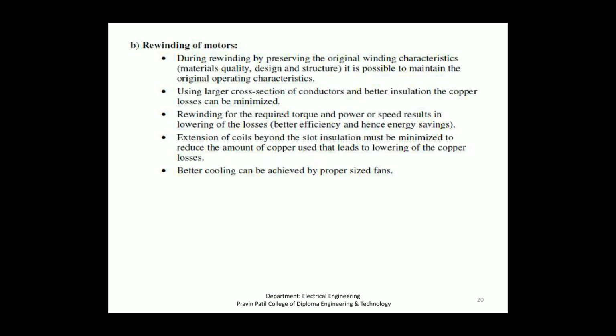A change in the air gap may affect power factor and output torque. Efficiency can be improved by changing the winding design, though the power factor could be affected in the process. Using wires of larger cross section would reduce stator losses, thereby increasing efficiency.